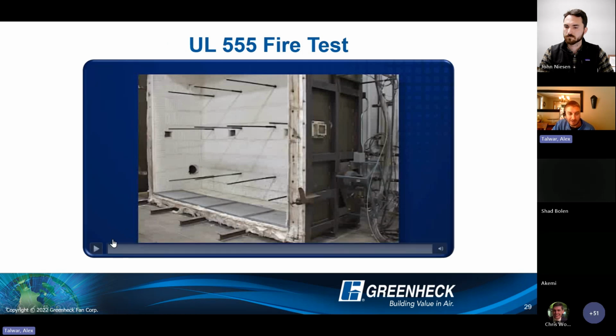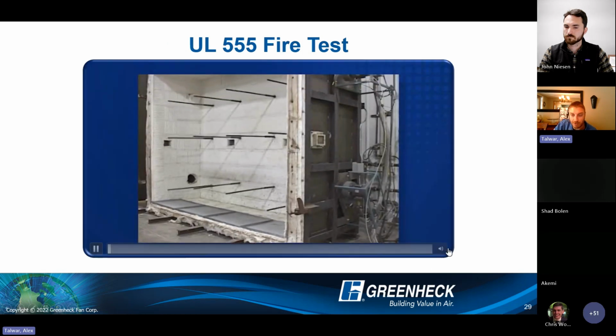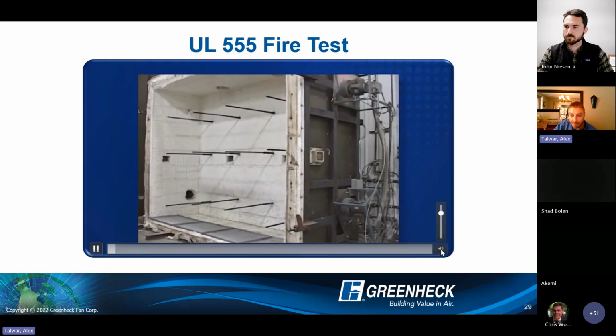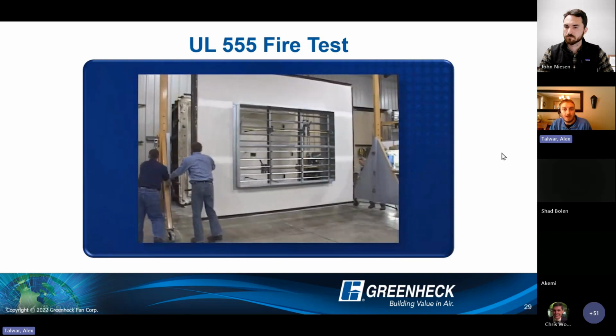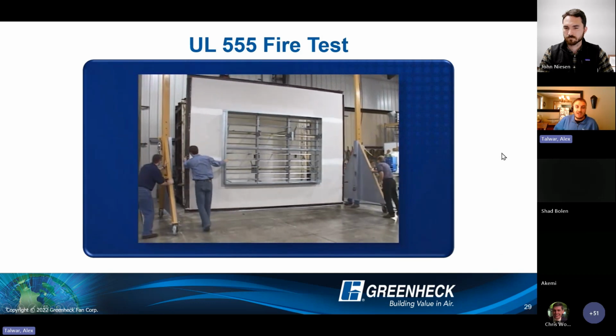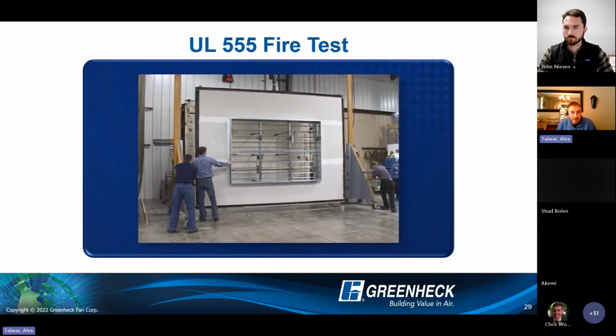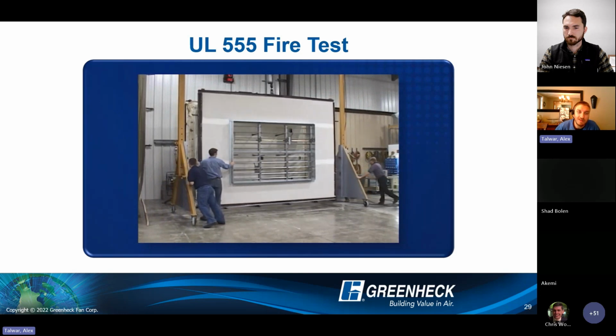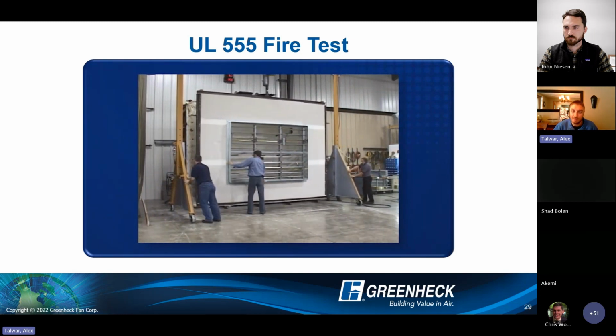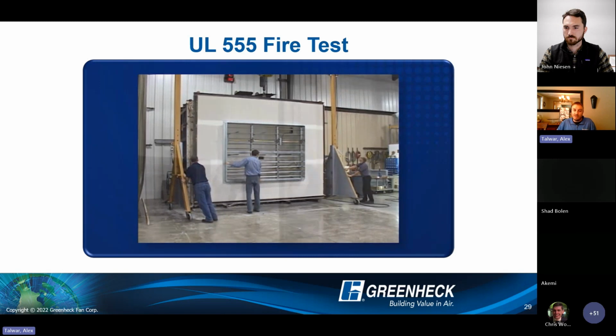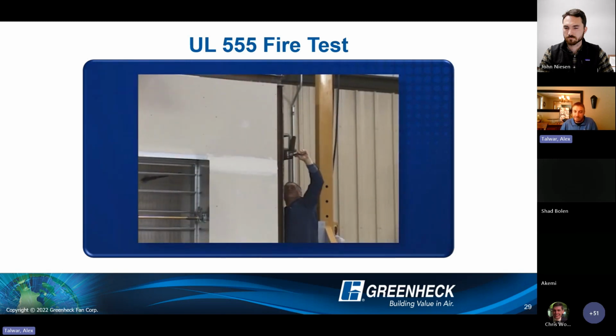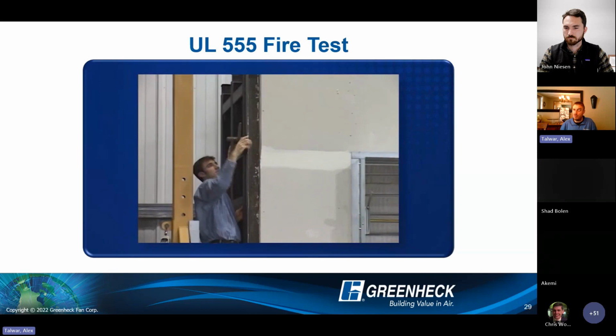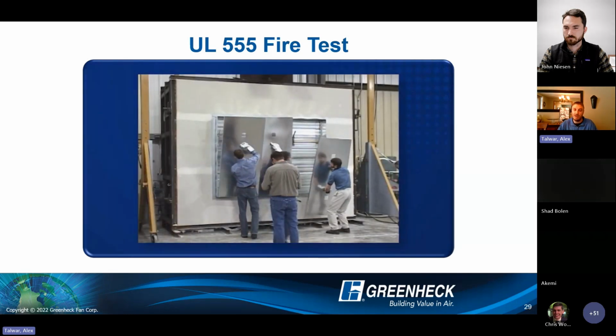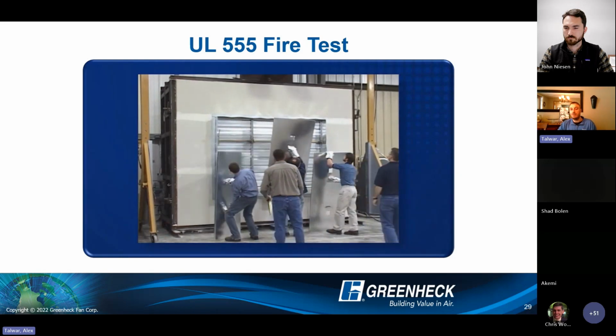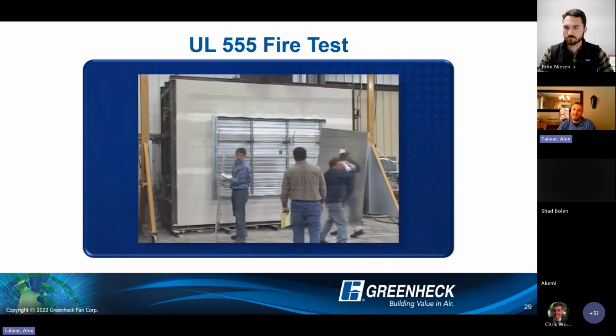All right, I probably don't have time to do this, but it's always so fun, so I'm going to show the fire test here. This is from our lab in Schofield, Wisconsin, a number of years ago. Actually, my boss is the lab manager, I think, in this video here. This is our large vertical test furnace, UL 555. It has 2.5 million BTU per hour burners on either side of the furnace, pumping flame into the furnace, following a prescribed time temperature curve.